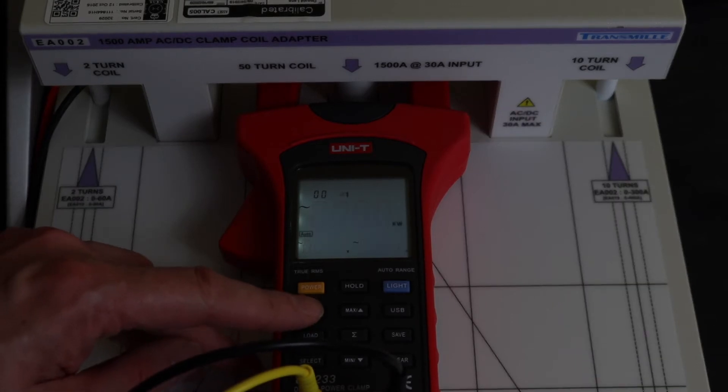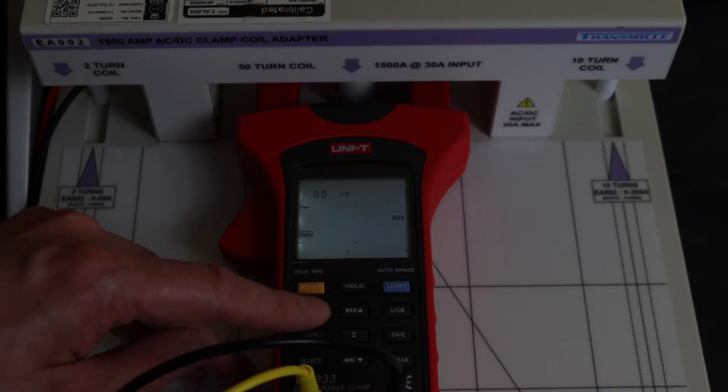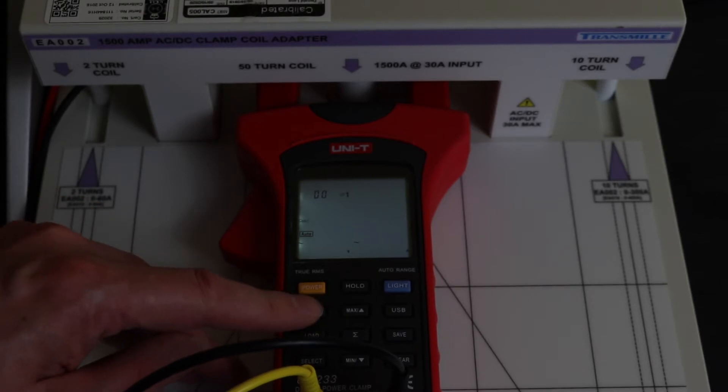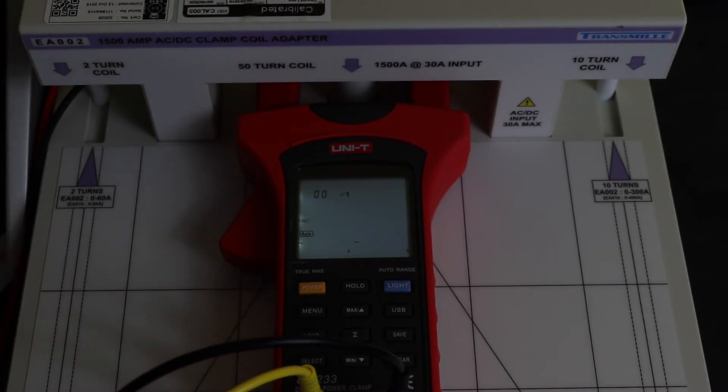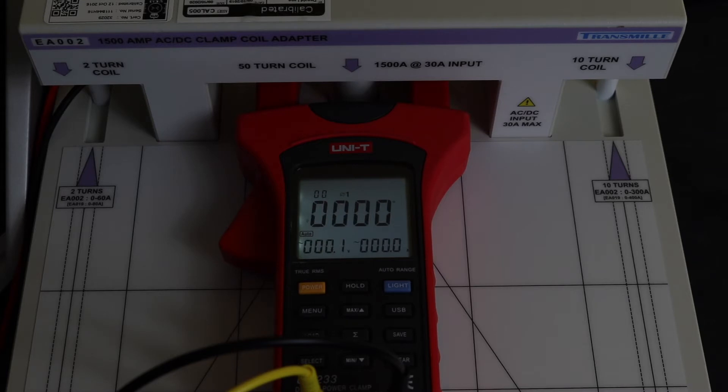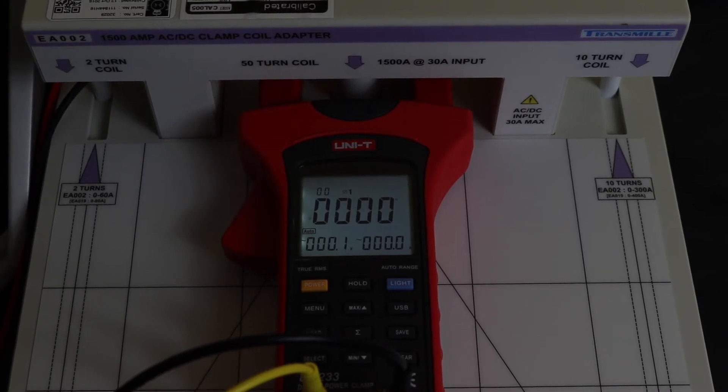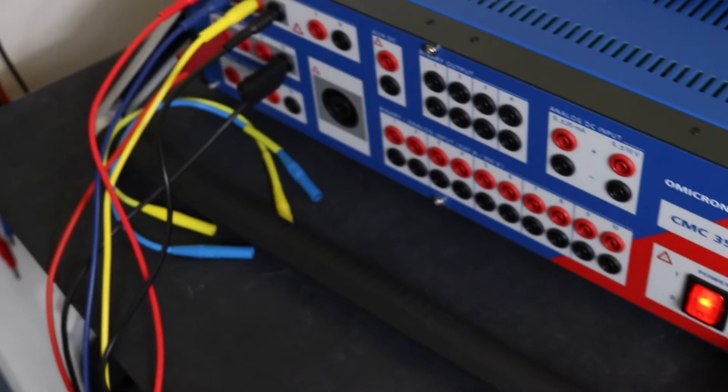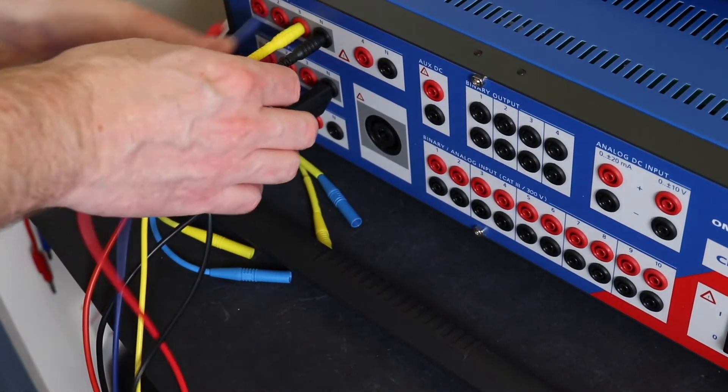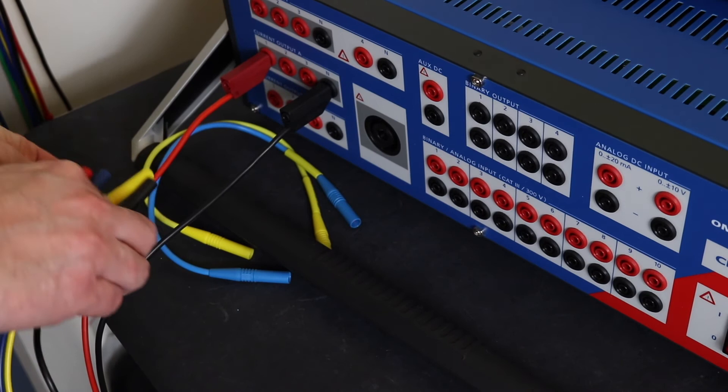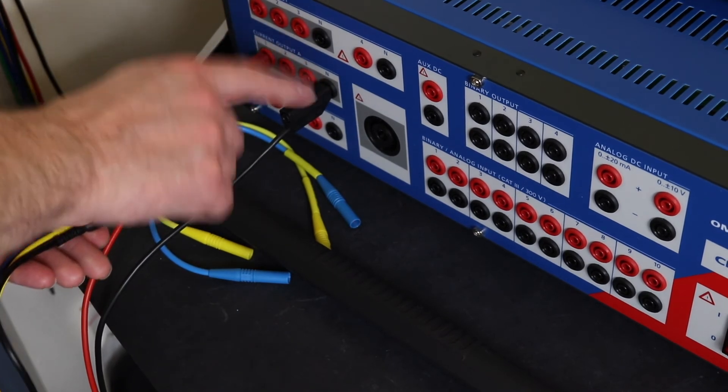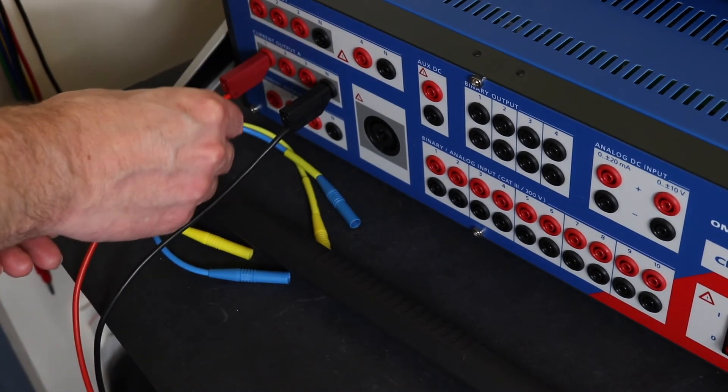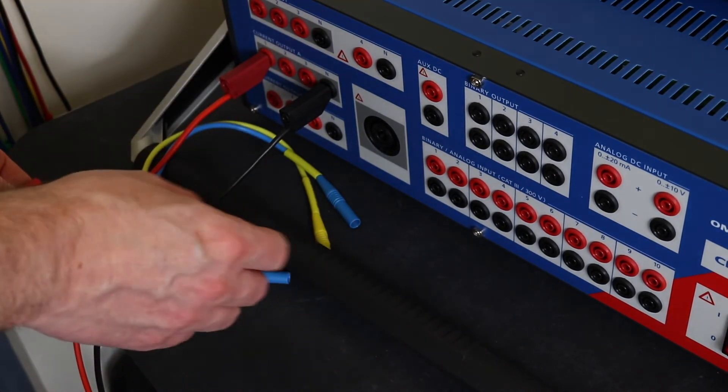is with the phase and power factor measurement. So there's the phase, there's the degrees there. I'm injecting one current just on the red phase. If I swing my camera around, you can hopefully see my connections.